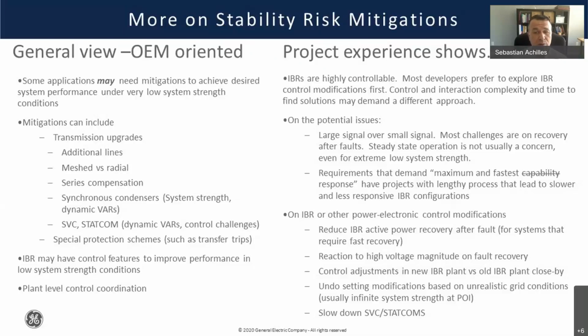The reaction to high voltage magnitudes on recovery is quite important. Weak grids or systems with low system strength are characterized by high voltages on clearing, like the recording I showed. That's very common. So how do you deal with those high voltages, making sure that equipment is not tripped, while at the same time, if you start absorbing reactive power to avoid the overvoltage, not ending up collapsing voltage? That balance of reactive power at the time of clearing is a very common subject of consideration.